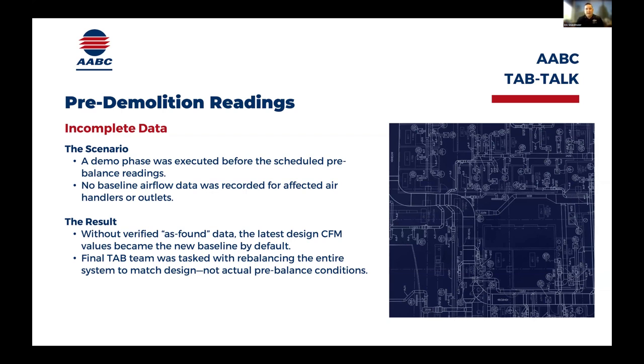So what ended up happening here in California, we have what's called OSHPD or HCAI, and they oversee all hospital construction. They're an overseer of the state of California that oversees all construction. So to get through a construction project in a hospital, you have to get through OSHPD. OSHPD came back and said, since you did not establish your pre-readings prior to construction or demo, now you are responsible for going back and reestablishing the latest design CFM for all of those areas. So we ended up having to rebalance 2 entire floors, supply, exhaust and return, because they did not call us out to do pre-readings to reestablish what that airflow was at post-construction. So that was the resolution.